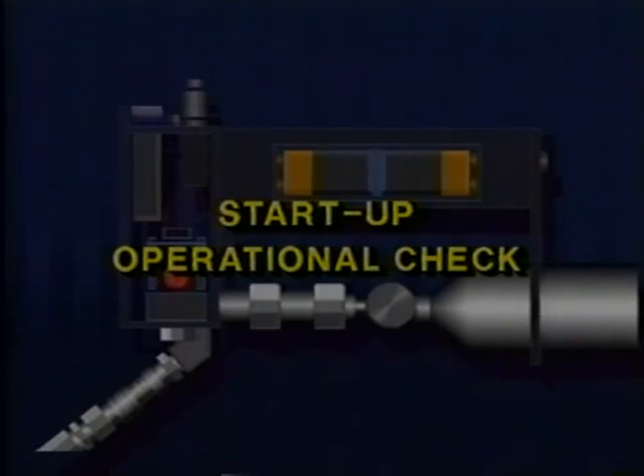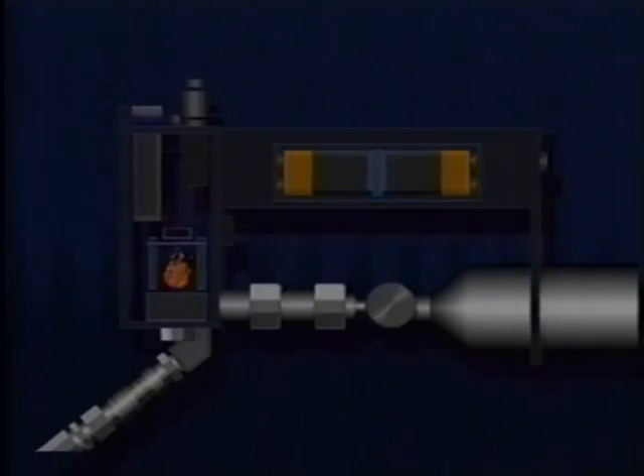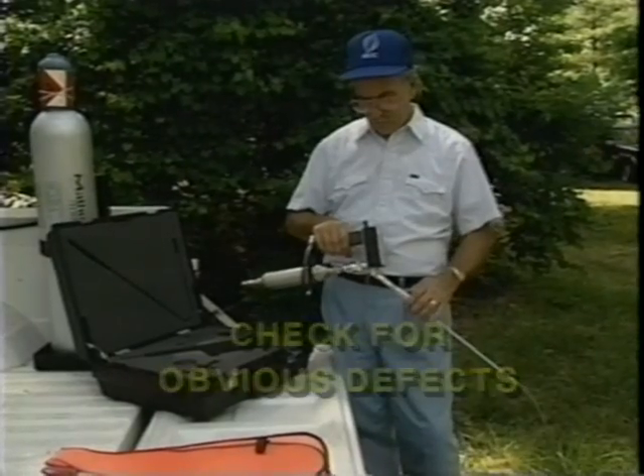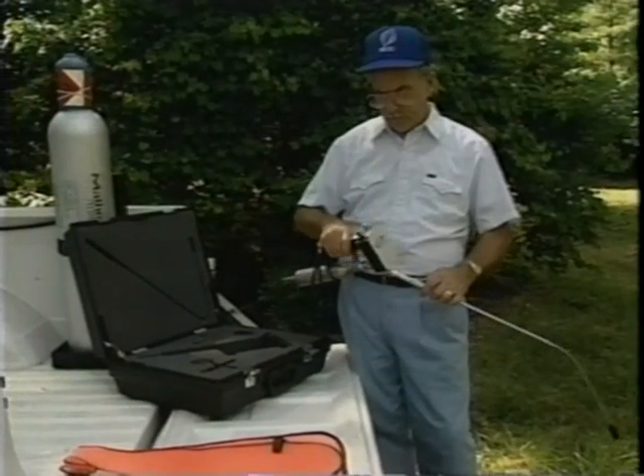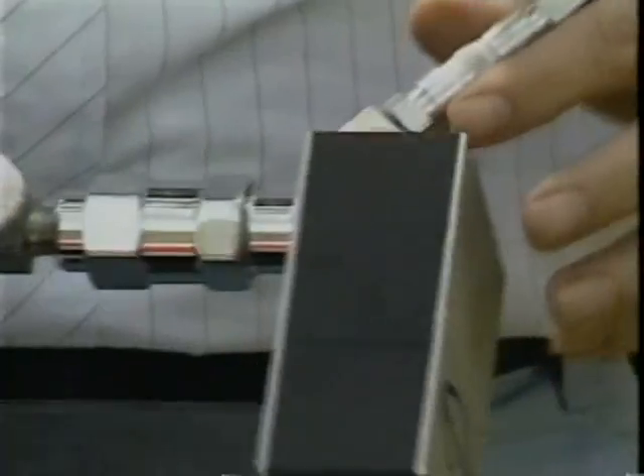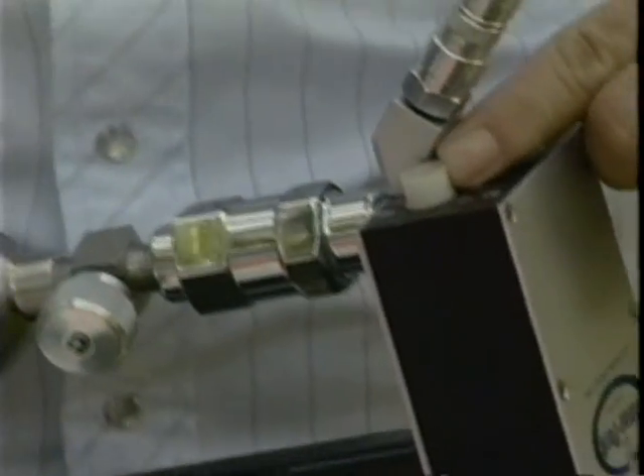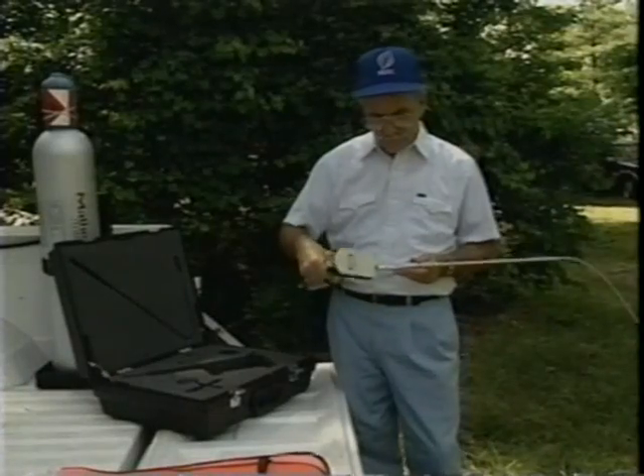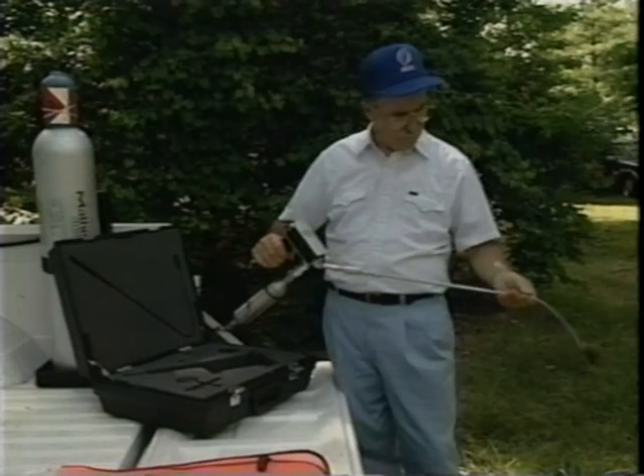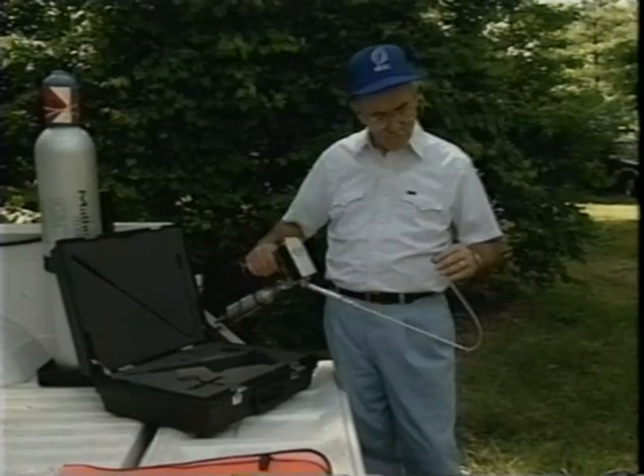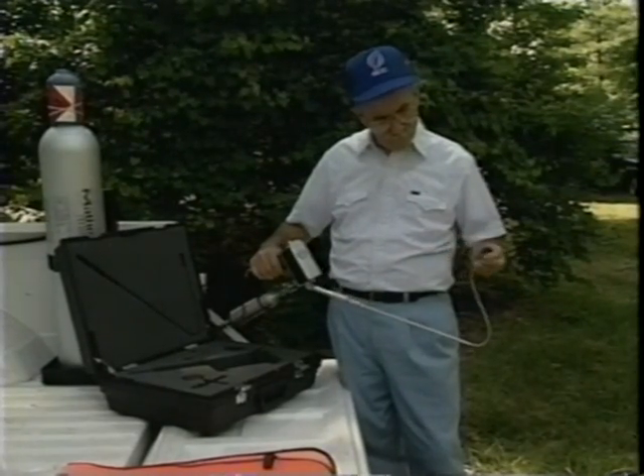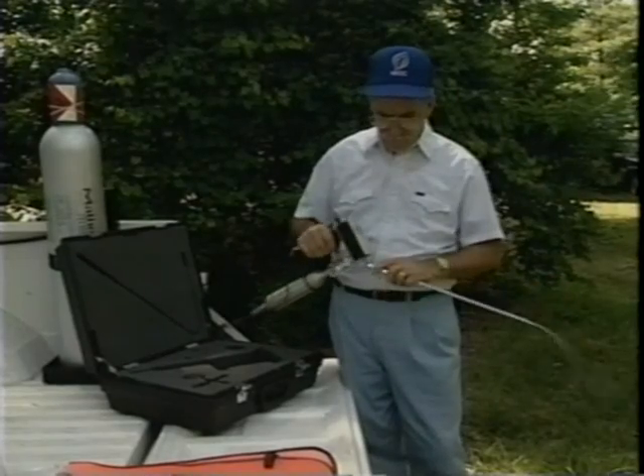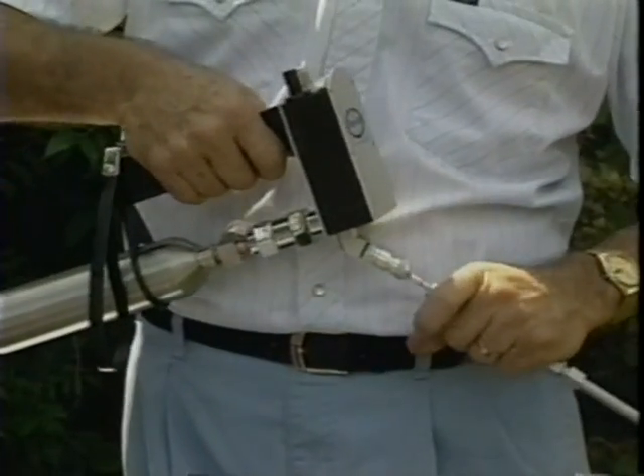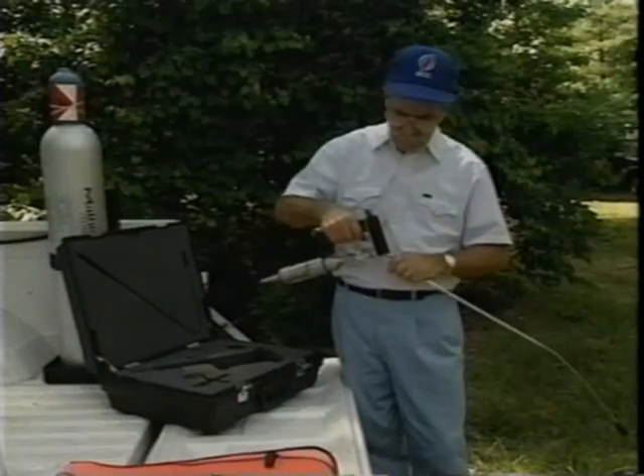After fueling, battery replacement, and filter replacement, the FlamePack 400 must be checked for obvious defects such as damaged or missing parts. First, make sure the exhaust flame arrestor is installed and in good condition. Be sure that the screens are in place. Inspect the sample probe for defects, damage, and obstructions, such as mud in the lower end. Connect the sample probe. It will snap into place when a secure connection is made.